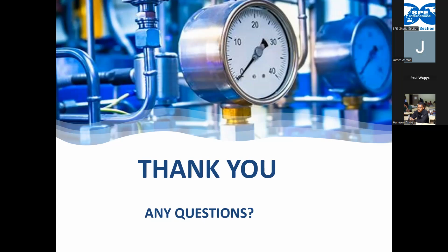Yes, please. But if I'm getting you right, let's use a flow valve for an example. If you have a flow valve and you want to open the valve by 15%, and then maybe by one or two errors from the system, it's open 15.9, 15.8. Is it the integral that will bring it back to the 15% opening?